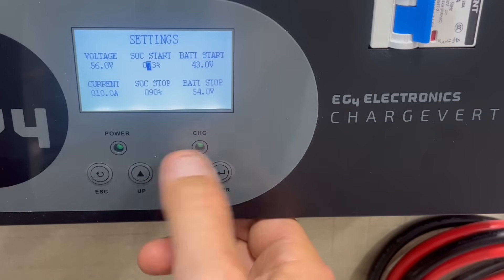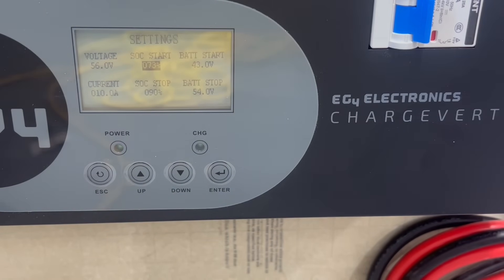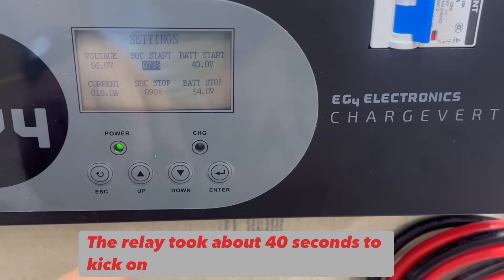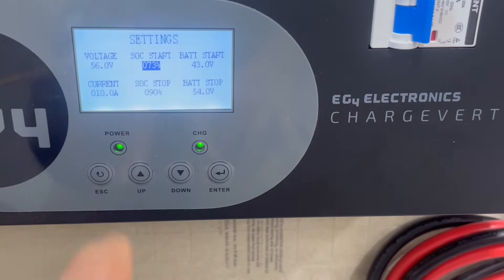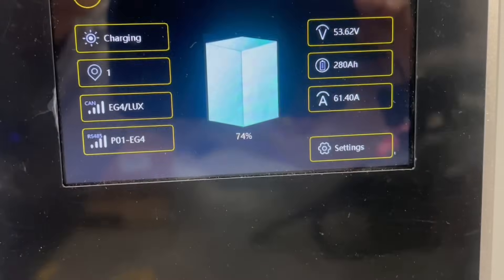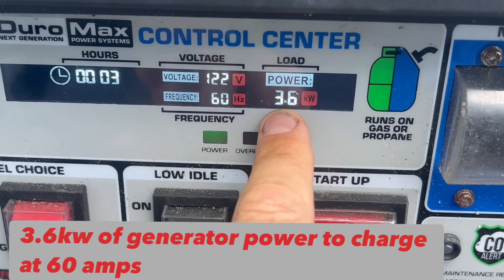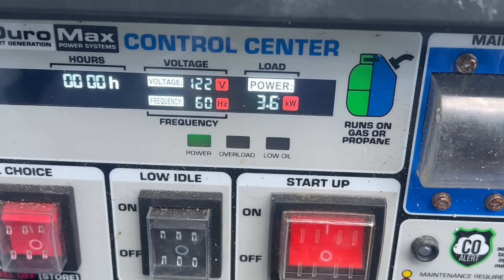Let's raise the state of charge start to 73% and see if it kicks the generator on. We're on — as soon as I walked out to the generator, it clicked on. We're right at 60 amps coming in. The generator reads 3.6 kilowatts of power — a little over 3,500 watts being used by the generator to put 60 amps into the battery.